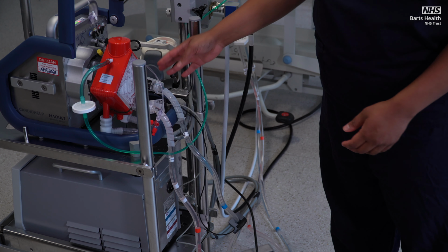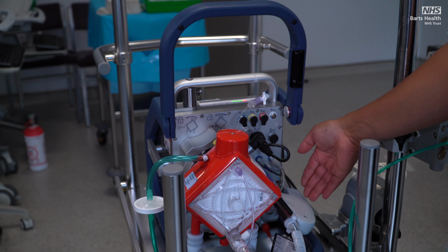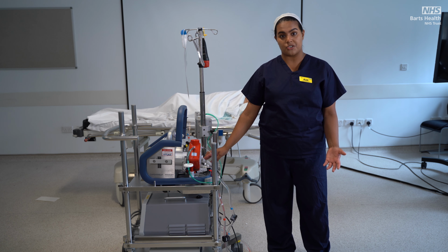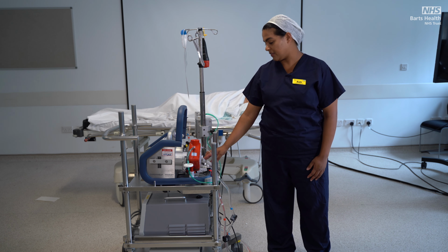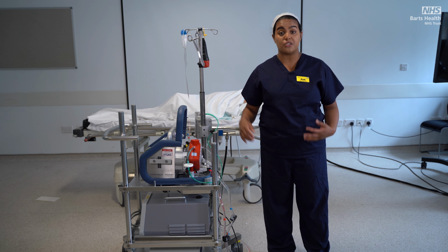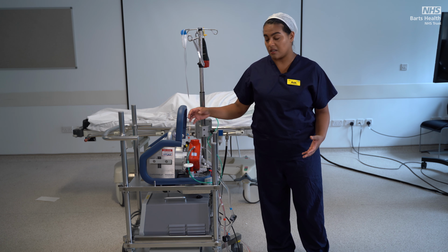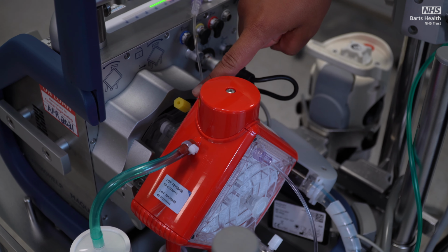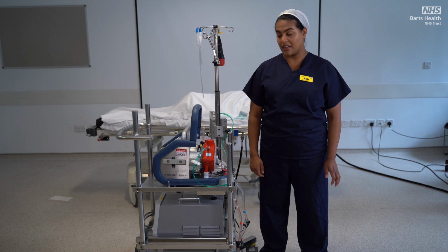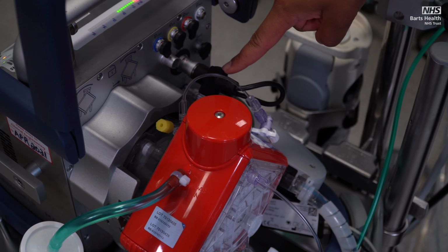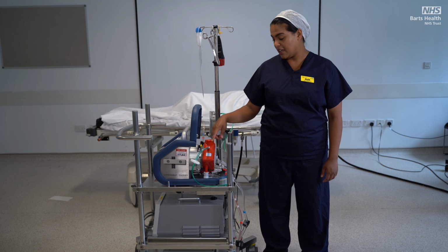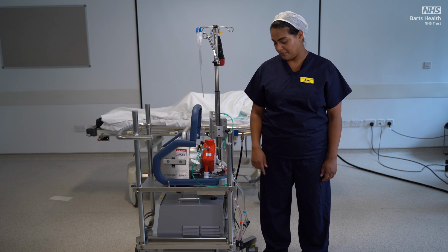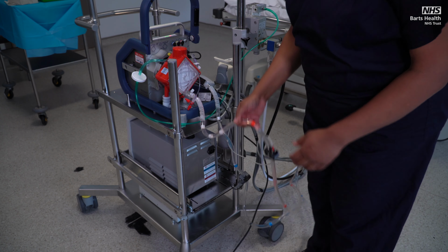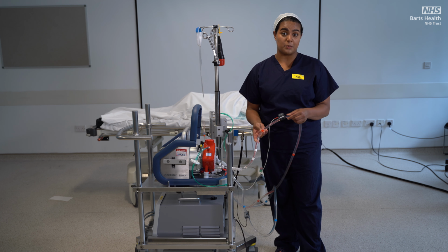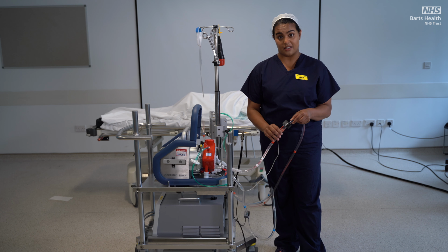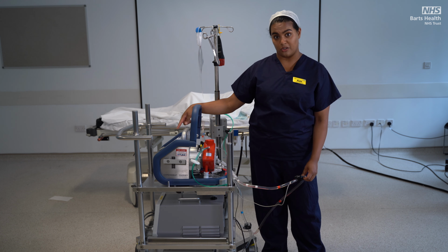It then makes its way past the venous saturation probe, where you can start monitoring your hematocrit and HB. Then it's going to make its way into the centrifugal pump, and any air is going to be vented through the yellow port. At the centrifugal pump is where we measure integrated pressure monitoring. Under positive pressure, it pushes the blood along the membrane, which then travels down the return line. Any bubbles will be detected by your bubble and flow sensor, and the flow will be displayed on your console.